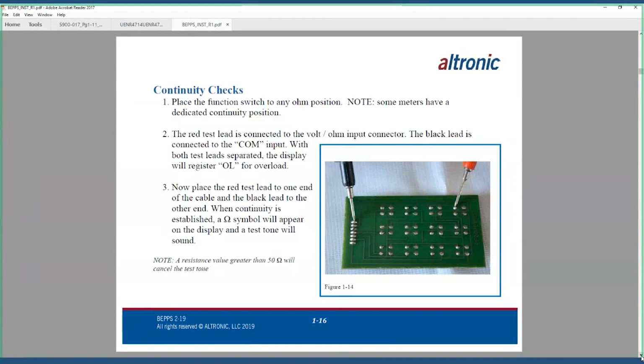It just gives you a nice buzz. There is a little bit of voltage produced by the meter coming from the red probe, and when it returns to the black probe is what triggers the buzz. A little bit more of a source voltage than the resistance test. So be leery of what circuits you're doing. Again, I generally only do this on circuits that are designed to turn things on and off. Never put your meter in a resistance test or a continuity test and go to an instrument such as a pyrometer or a channel on a DE3000 or 4000 that is designed and or has dip switches set up currently to read thermocouples, because you will damage the circuit on the board.